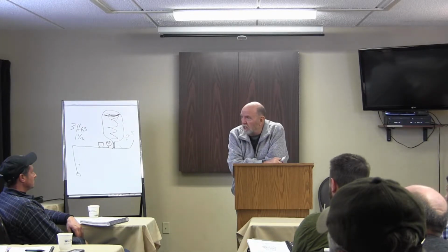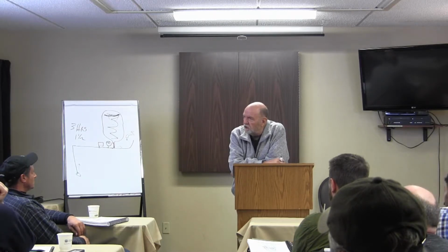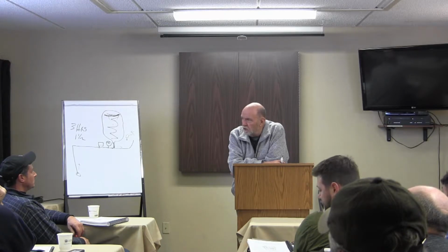It'll be on less. Simple. Electricity costs money. This whole system was designed so that if I'm running water for a total of 3 hours of the day, I'm only using an hour and a half of electricity. That's the money we're saving. It's not to save the life of those pumps, I'm told; that's the last reason. Those pumps will go forever. The shallow well pumps you see in houses are 30 years old. They're always old suckers because most everybody tries to go to drilled wells these days. Those pumps last forever. That's what I thought too for the first 10 years, until I talked with somebody who said, hey, it's about the electricity. And that made sense.